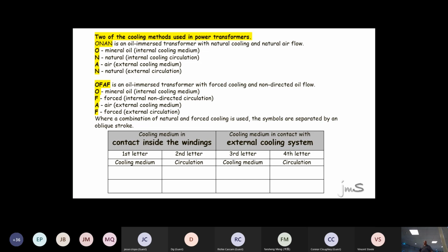The first letter can either be O or A - O for oil, A for air. If I say O, what is it? Oil - that's oil pumping down through the windings. But is that oil natural or forced? Forced means there's a pump circulating it; natural means it's just lying there.